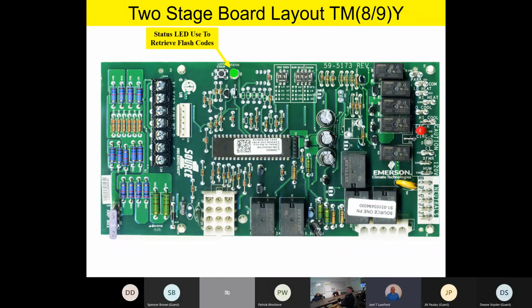Right next to the last error button, we have a status LED. It should be noted this LED will flash error codes if you have error codes, but it will also show you normal operation. If you take a look at the service information that comes with the equipment, in the install information, you'll be able to read about all those flash codes and what they mean. It should be noted that LED will flash either green, yellow, actually, I believe the service manual calls it amber, but it looks yellow to me. So green, yellow, or red. That tricolor LED is designed to flash 3 colors, and we just have that single LED right there on the board. So it's very, very handy. The technician can look at that. He can not only see existing flash codes, he can also find out the last 5 errors if he depresses that last error button right next to it. Any questions or comments on that?